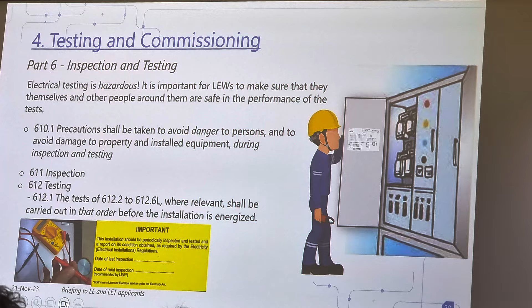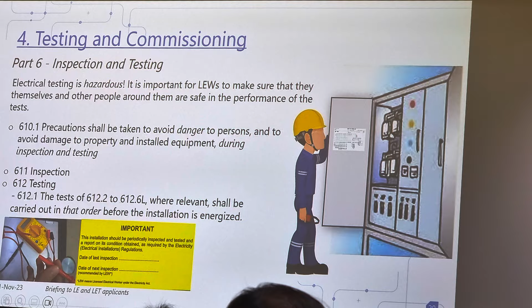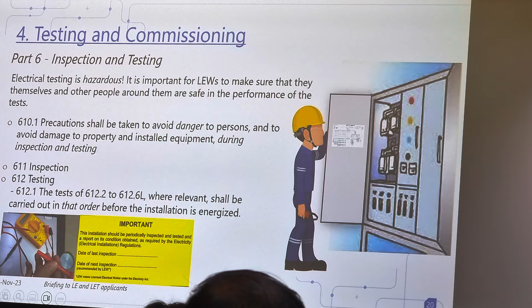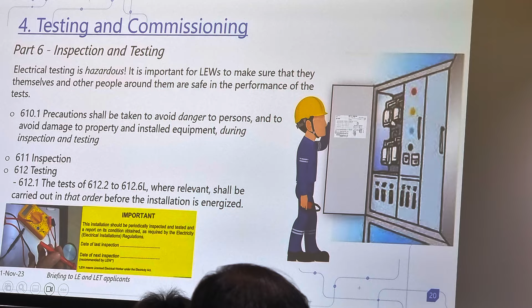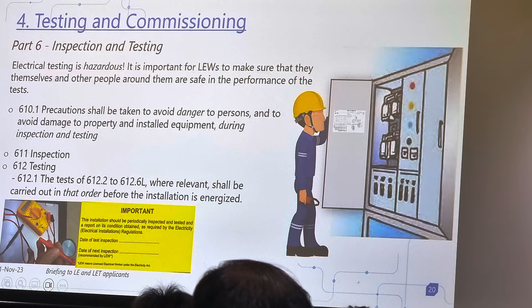Testing is this one, chapter 1, 612. And again, in chapter 612, 612.1, the tests are described. And not only that, the order of the test is also important. The code specifically mentioned. That means that you should follow the sequence of the tests. Why? Again, because the test itself could be hazardous. There are certain tests that you need to inject the current, you need to inject the voltage. You must make sure that some basic test is done first. That's why the code say you need to follow the sequence.